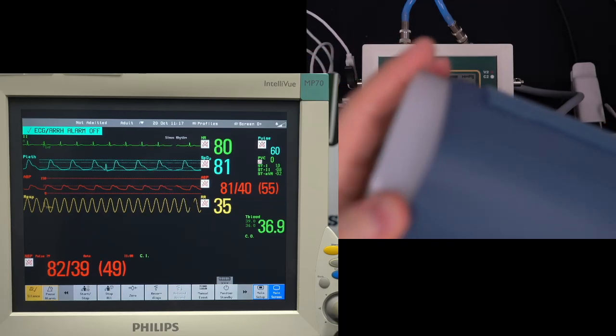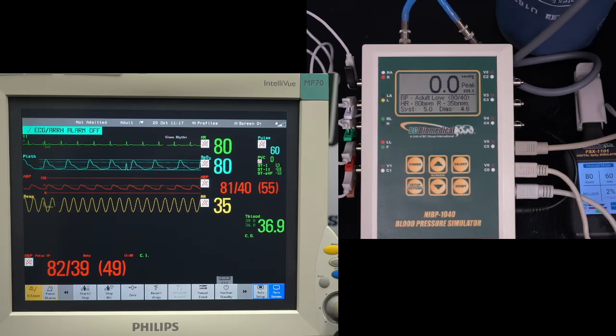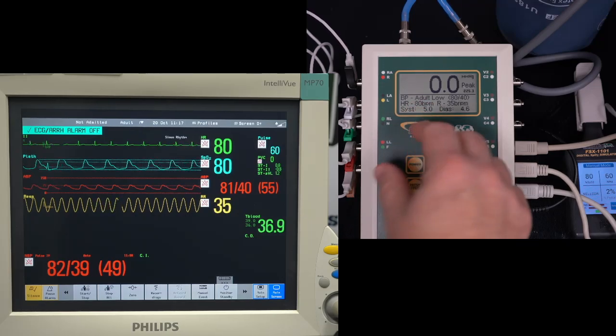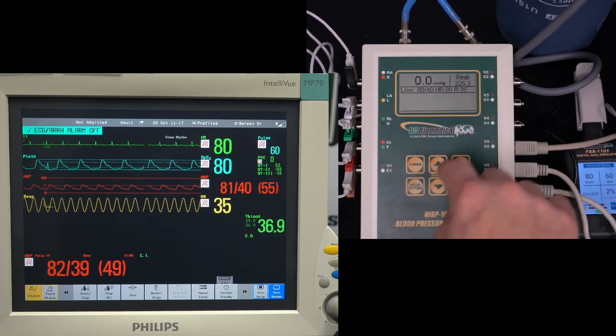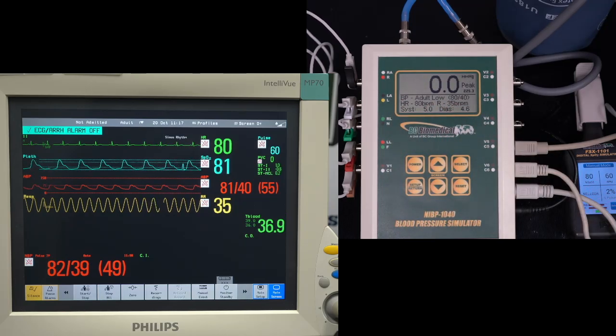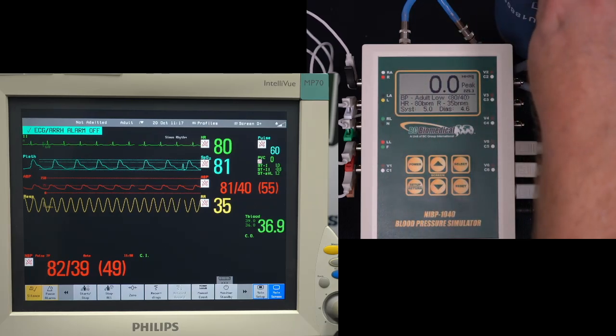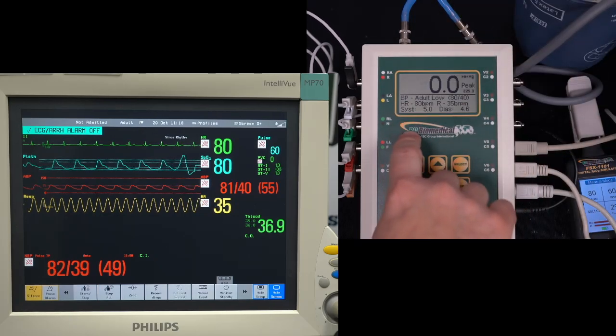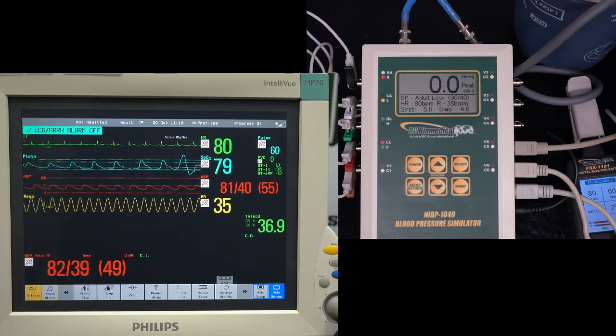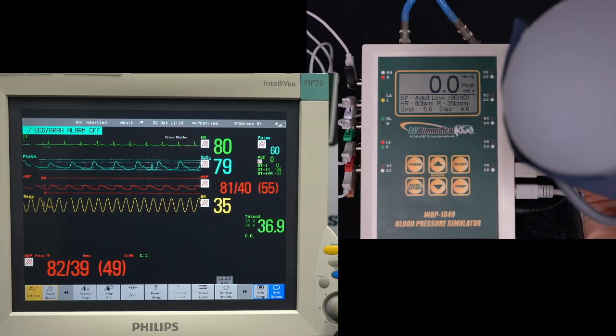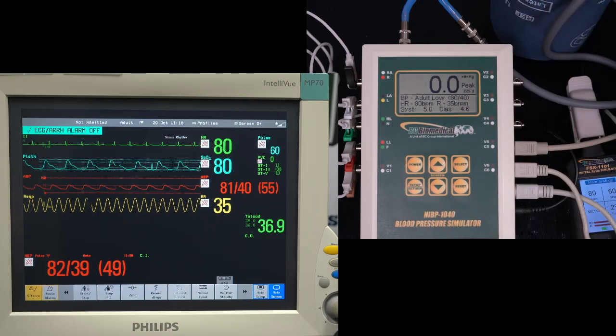Really what's happening is the monitor is looking for a pressure signal that would typically come from your arm. So you want an arm-sized cylinder there. If that cylinder isn't there, then it's trying to fill that bladder, the cuff, with air, and you've got a whole lot of volume of air in there. Inside here, there's a fixed volume that we saw on the motor screen, our pulses that we're simulating, to simulate a heartbeat. So if there's a really large volume of air in this cuff and a relatively small volume in here, the monitor's not going to see much of a signal, and it's going to be hard for it to get that reading. But when you wrap it around something firm, that gives it a good consistent measurement. So the exact object doesn't really matter. You want it to be about arm-sized.